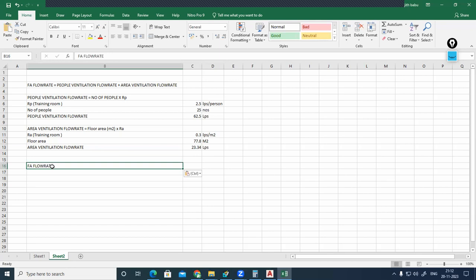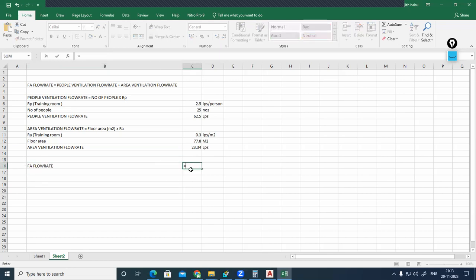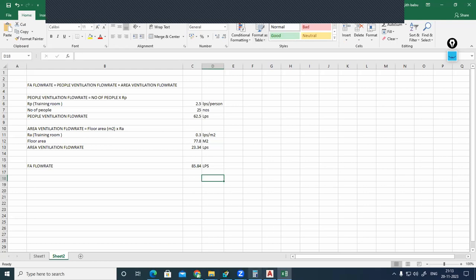Now we can find the fresh air flow rate or outside air requirement. You can add together, your fresh air flow rate will be people ventilation flow rate 62.5 plus area ventilation flow rate 23.34. You need 85.84 liter per second. So this people ventilation flow rate plus area ventilation flow rate, manually we can calculate. So we found that overall 85.84 liter of air has to be introduced within the space to maintain the indoor air quality. Okay. How we can introduce that?